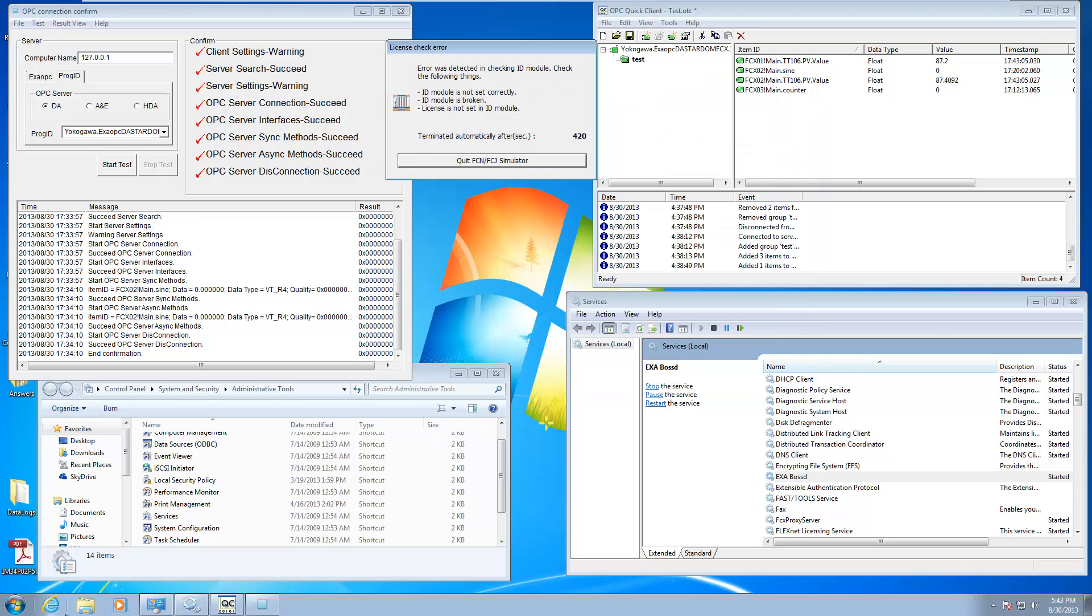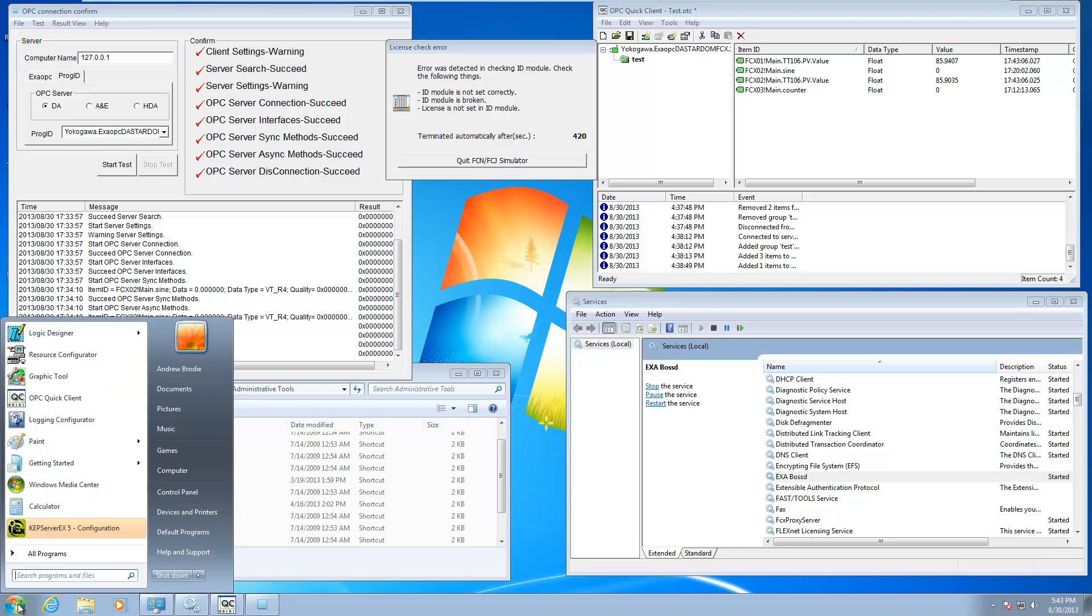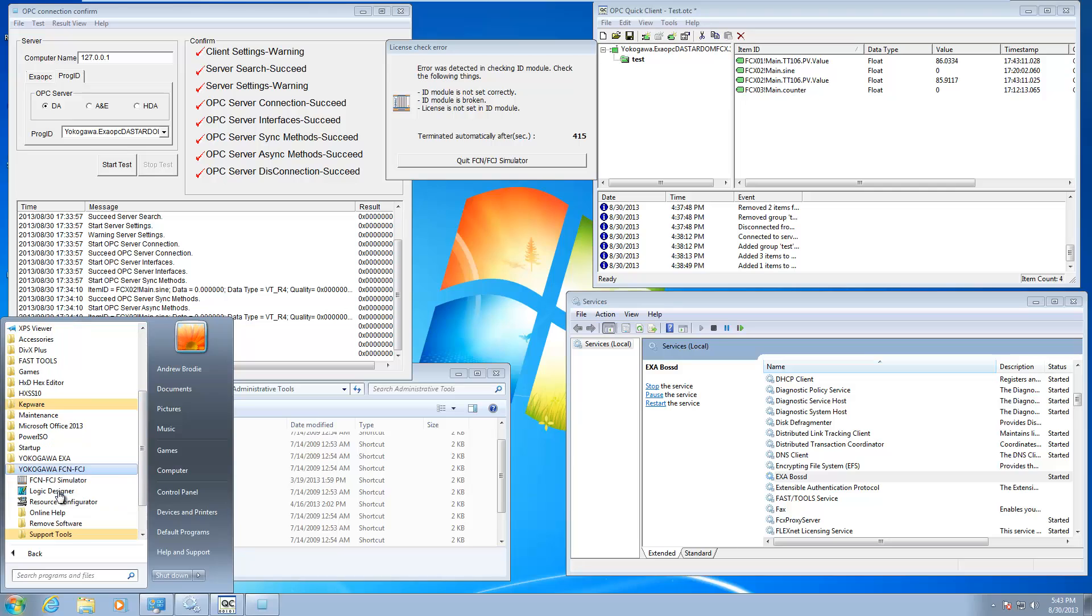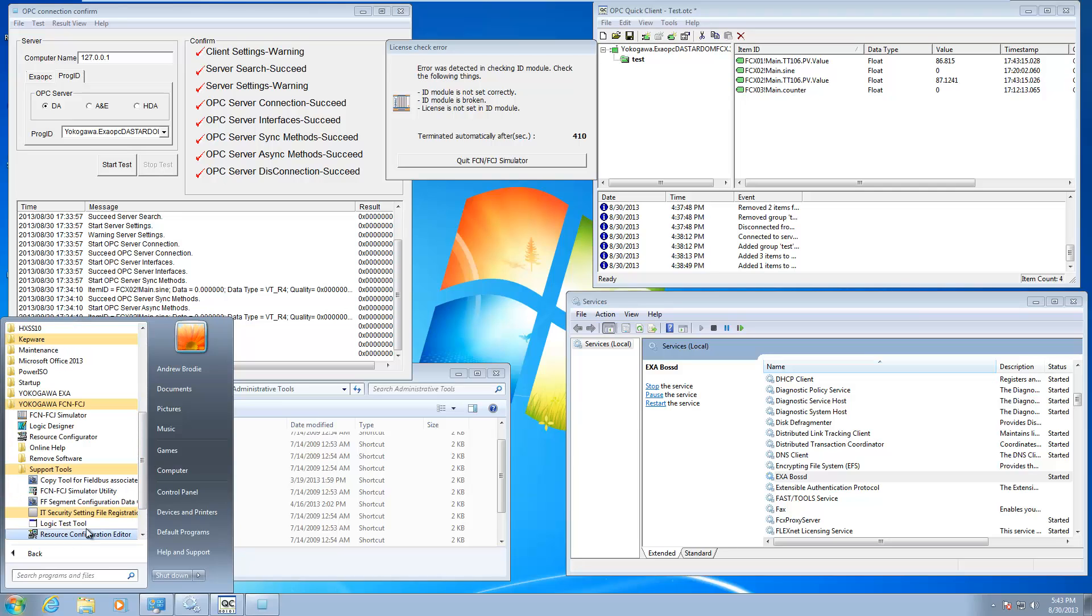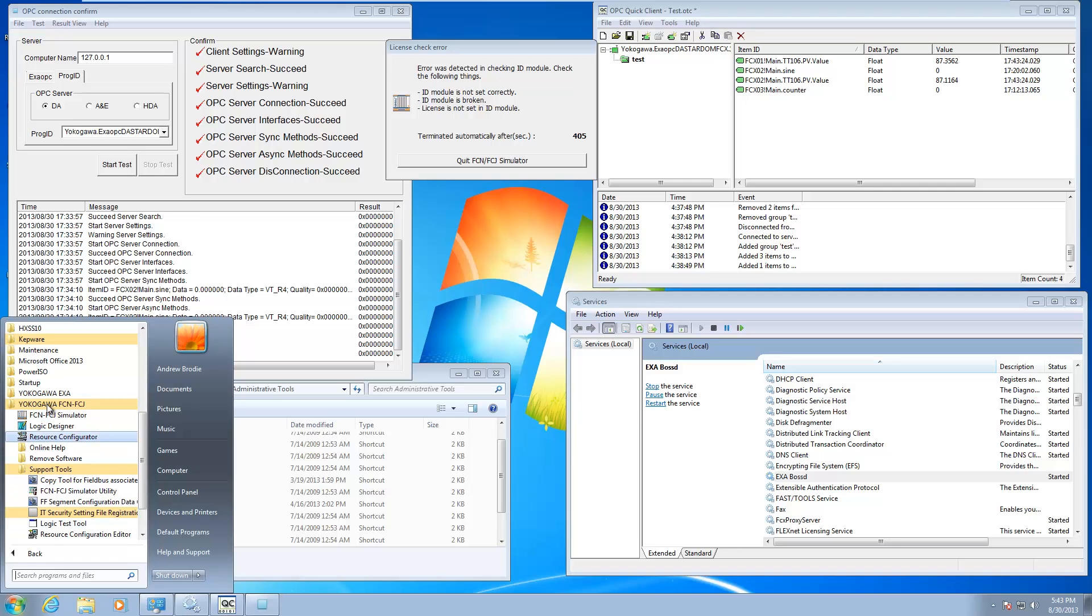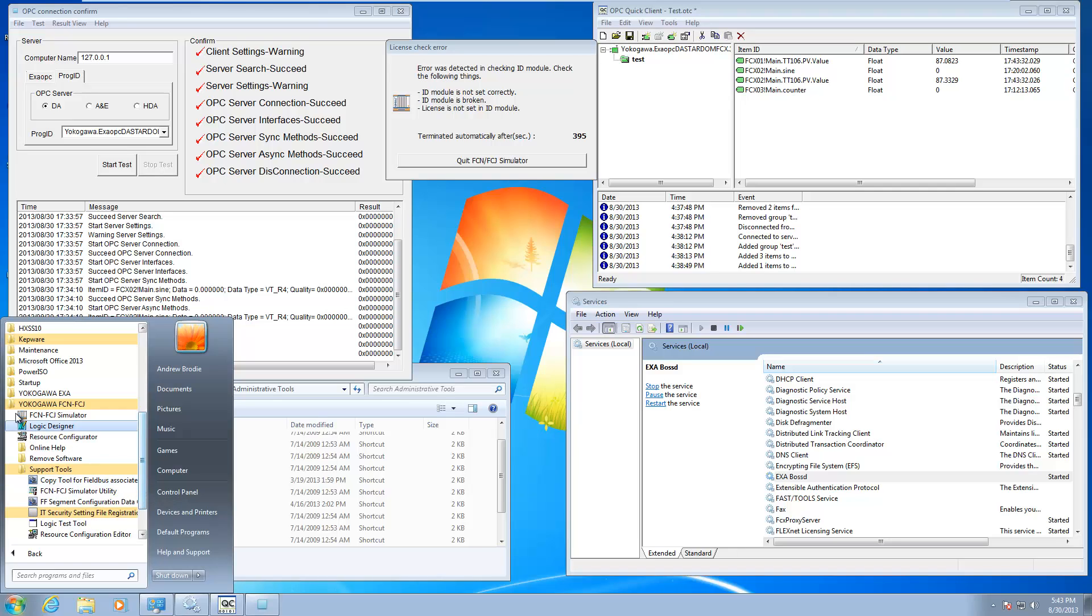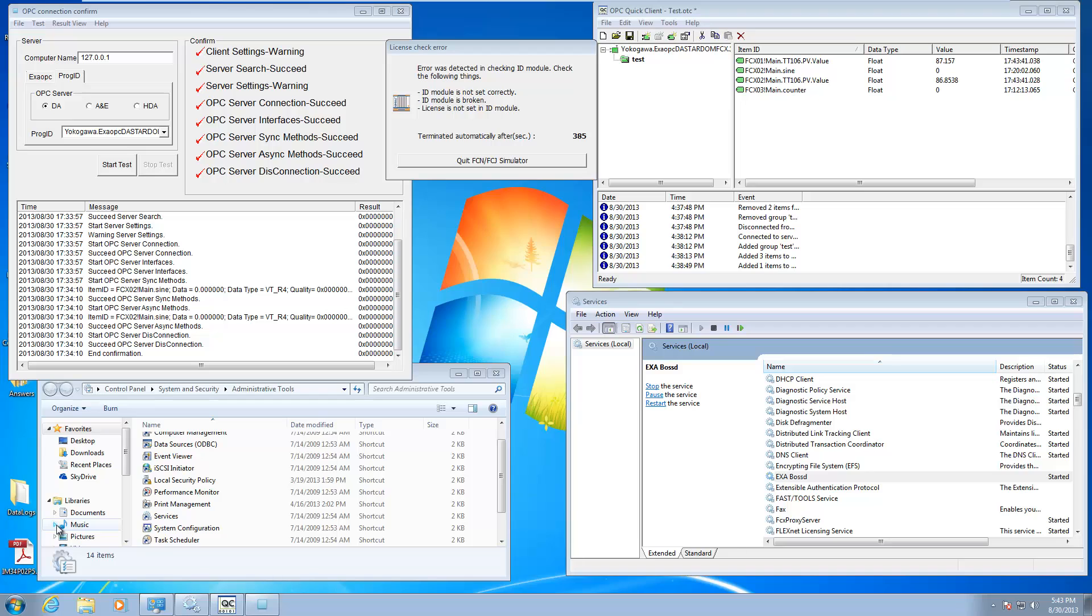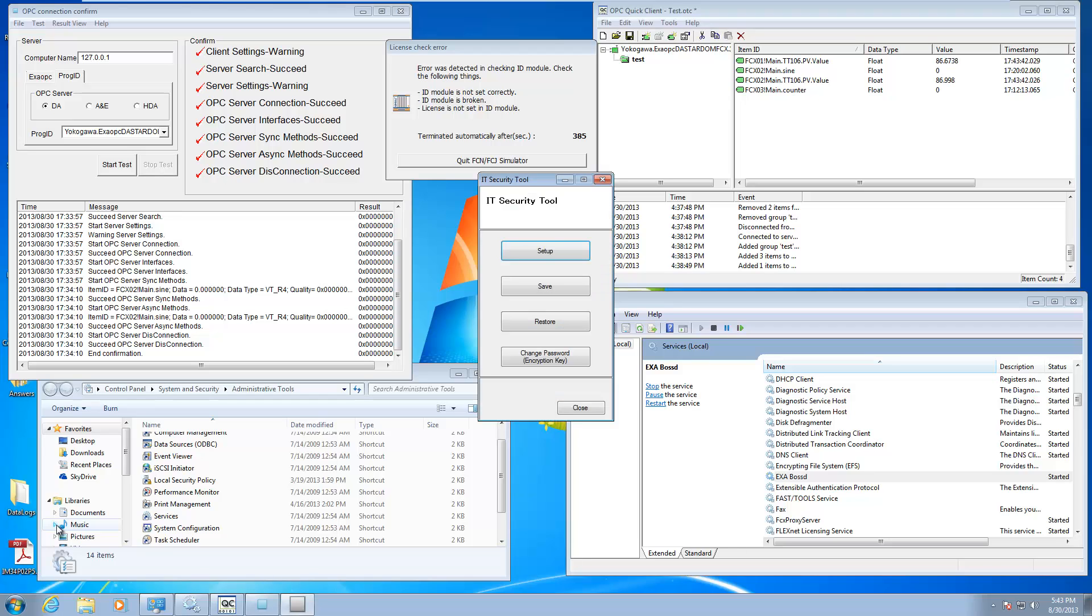The next thing you're going to want to do is since you installed that security tool, you're going to want to go under FCN FCJ and support tools. You're going to want to run the IT security file registration. This will go ahead and everything that you've installed has a little security file associated with it. It's going to register that with the IT security tool. Once you've done that, you can go here to Yokogawa security and run the IT security tool.